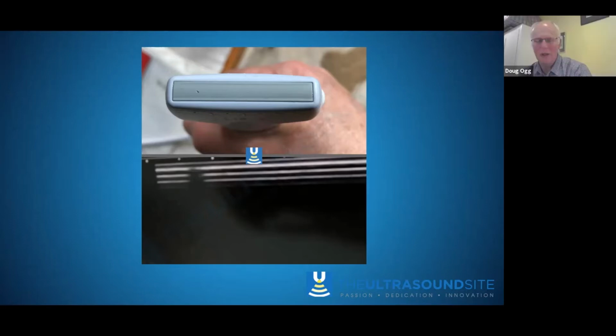Okay, so the dropout, because this actually happened on one of our probes. Dropouts, the crystals. I dread to say that, but it is actually what happened. When we tested the probe, there wasn't any dropout at that point, but the acoustic lens had been damaged, and because the voltage goes onto the transducer, actually the electricity could leak out at that point.